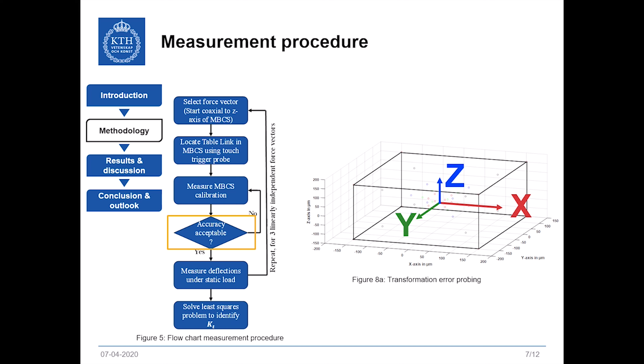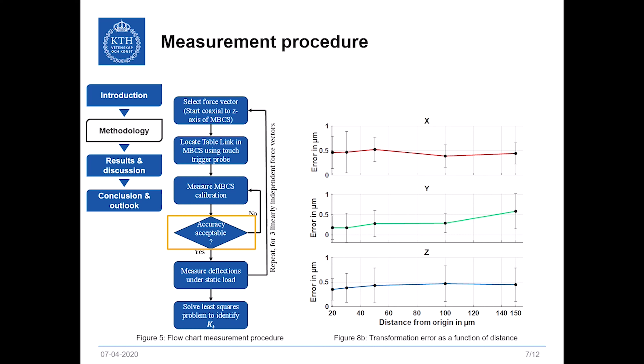Figure 8b shows the transformation error for the Cartesian components x, y and z as a function of the distance from the origin position. In the range of the measured deflections, the error of the transformation was less than 1 micrometer, which ensures a test uncertainty ratio of at least 5:1, as the maximum applicable load is 700 Newton and the stiffness in the z-axis is expected to be at most 125 Newton per micrometer.